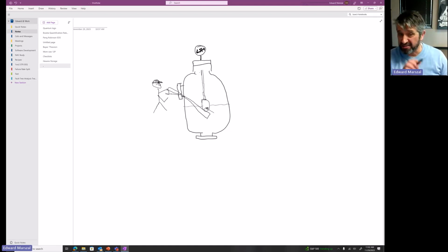Not only does this test I just showed you not detect that that failure mode has occurred, it can actually cause that failure mode to happen. I stuck my 2x4 in, I poked a hole in the float, and I went through the test and said it's working, but my test actually caused the device to fail.